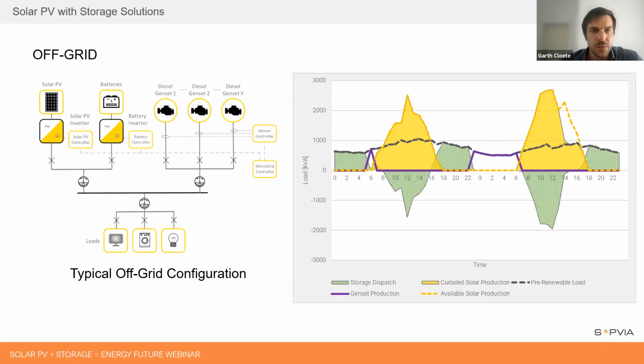In this case and the next two, we're taking solar PV plus batteries and adding them to the existing diesel generator fleet. This requires significantly oversizing your solar PV source to run in parallel with your batteries, since you're using so much of that solar PV during off-peak or night time. The rough single line diagram on the left is one example—there are lots of different configurations, like DC-coupled PV onto battery, or splitting essential and non-essential loads—but this is just one specific example.